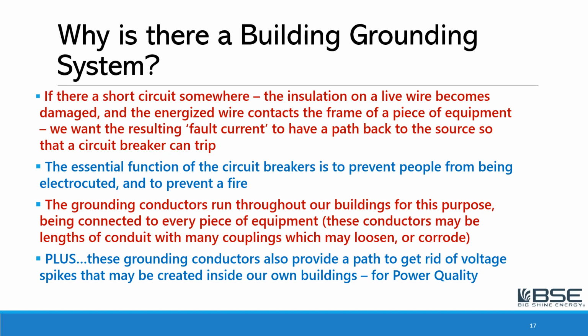Every so many feet, they put a coupling. Over time, if the couplings corrode or become loose, or there's a little lock nut at the box or panel that becomes loose or corroded, then the resistance of that ground circuit can increase. So all of those are things that need some maintenance and some inspection. Also, grounding conductors provide a path to get rid of voltage spikes that may be created inside our own building for power quality. So the grounding system performs an essential role in reliability for all that electronic stuff that we're adding to our buildings today.